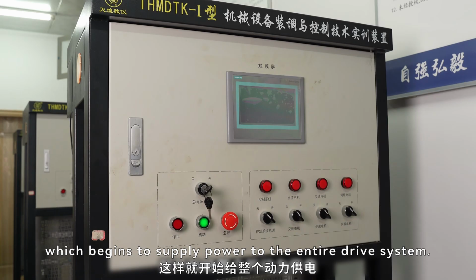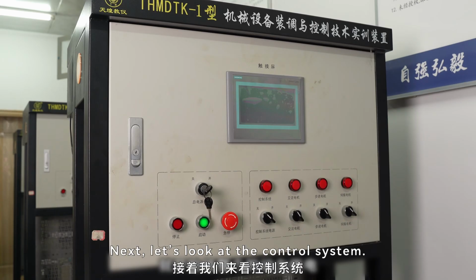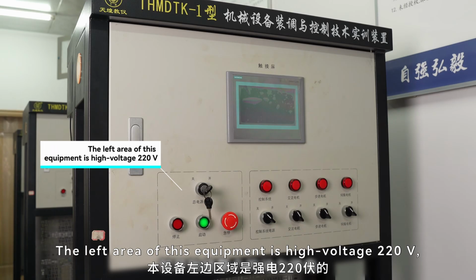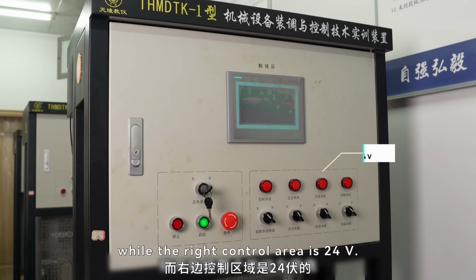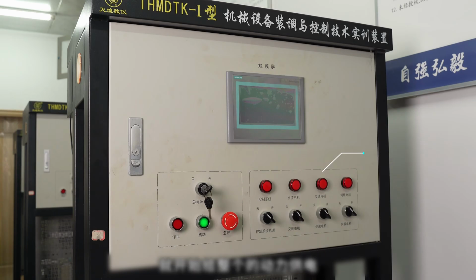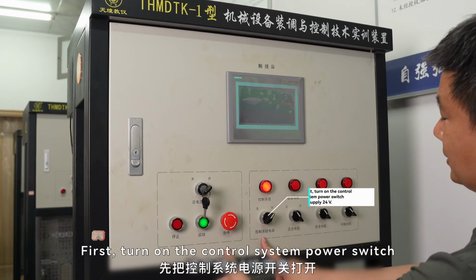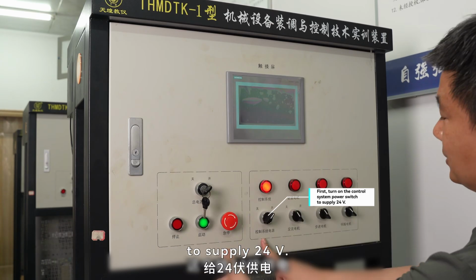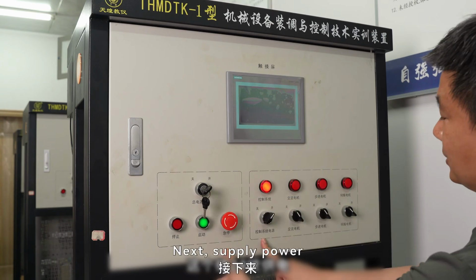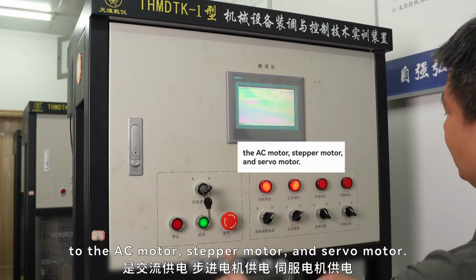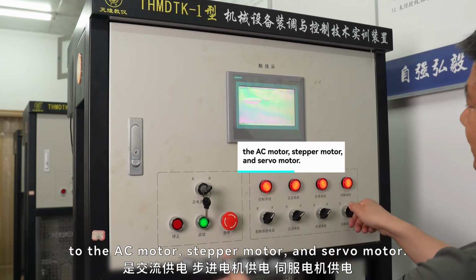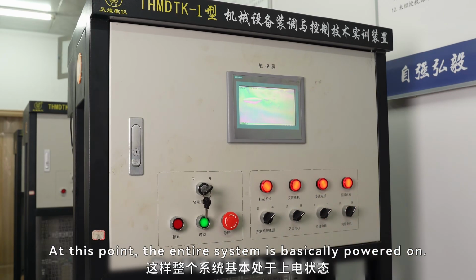drive system. Next, let's look at the control system. The left area of this equipment is high voltage 220 volts, while the right control area is 24 volts. First, turn on the control system power switch to supply 24 volts. Next, supply power to the AC motor, stepper motor, and servo motor. At this point, the entire system is basically powered on.